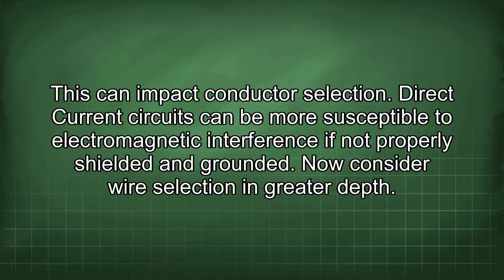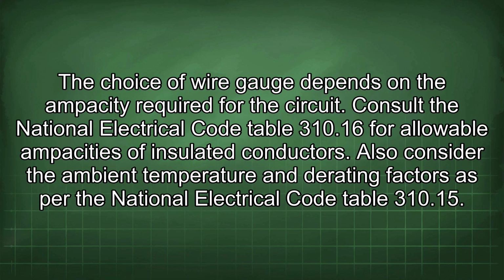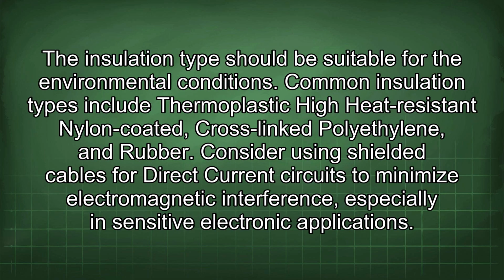Now consider wire selection in greater depth. The choice of wire gauge depends on the ampacity required for the circuit. Consult the National Electrical Code Table 310.16 for allowable ampacities of insulated conductors. Also consider the ambient temperature and derating factors as per the National Electrical Code Table 310.15. The insulation type should be suitable for the environmental conditions. Common insulation types include thermoplastic high heat resistant nylon-coated, cross-linked polyethylene, and rubber. Consider using shielded cables for direct current circuits to minimize electromagnetic interference, especially in sensitive electronic applications.